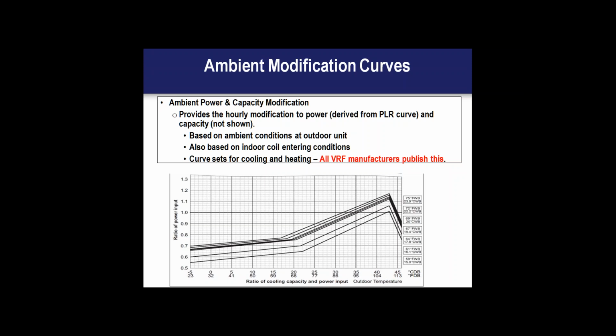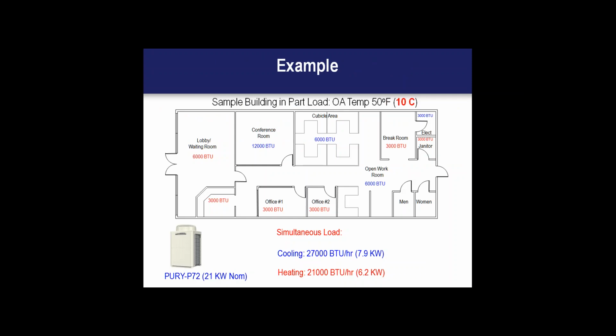Mitsubishi tends to provide it graphically, as a family set of corrections based on outdoor conditions and evaporator inlet conditions. You'll have two graphs for cooling power and capacity correction, and two graphs for heating power and capacity correction. To put this in perspective, let's look at a simplified example. We have a small office building at an ambient temperature, at a particular hour, of 10 degrees C, served by a 6-ton or 21 kW nominal simultaneous system. Taking just an hour snapshot, we have a total load of around 7.9 kW cooling and a heating load of 6.2 kW.